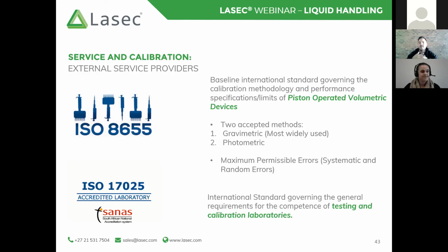There are two methods that are widely accepted. The first method being the gravimetric, as you would have seen in our corporate video at the beginning of this webinar, which showed the calibration facility. We use the gravimetric method, whereby we weigh the amount of liquid that's being pipetted. Another method is the photometric method, although not as widely used. It is still covered in this ISO standard.